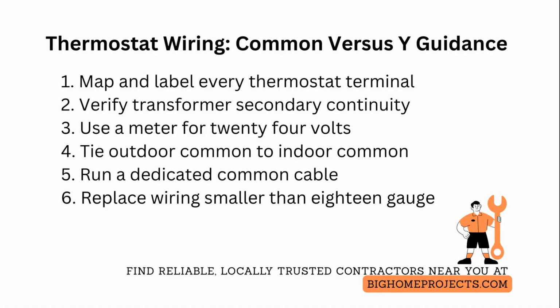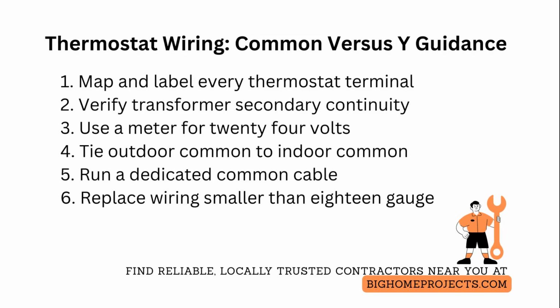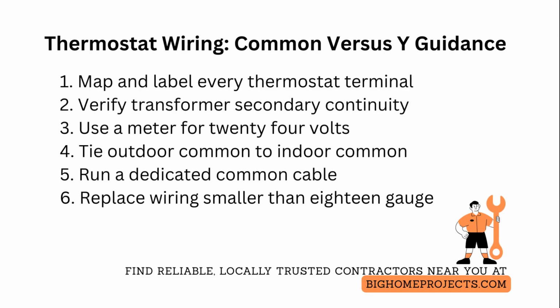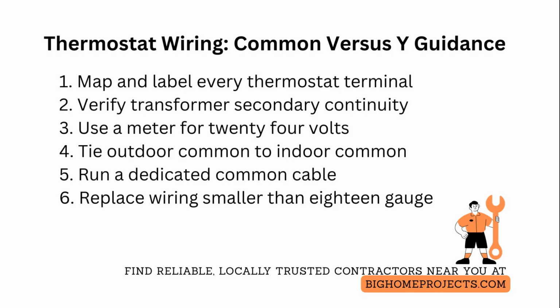If you encounter intermittent contactor engagement after rewiring, check for loose crimps, corroded terminals at the outdoor unit, and voltage drop under load. Replace wiring smaller than 18 gauge for runs over 50 feet. Finally, before powering up, verify the thermostat programming does not try to switch the common for other functions, and label the panel with the true function of each conductor for the next technician.